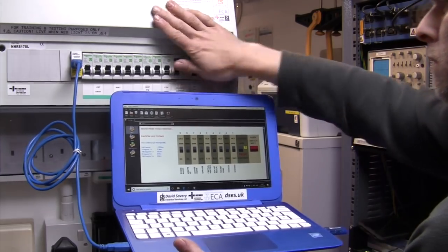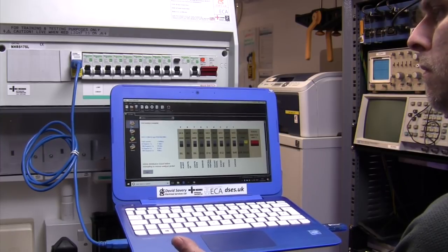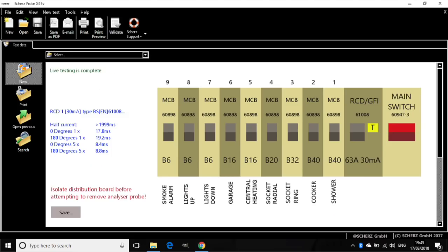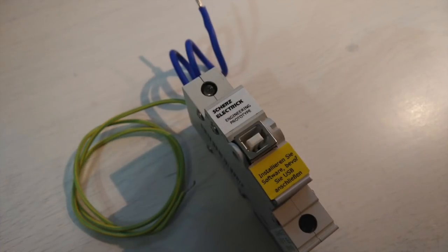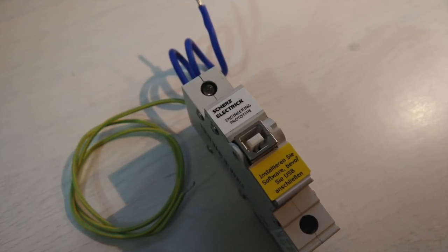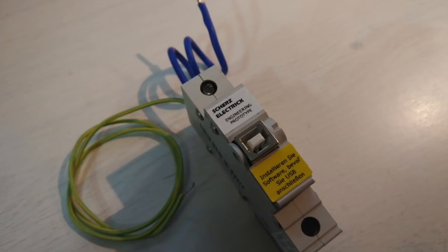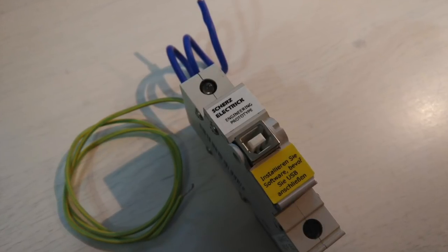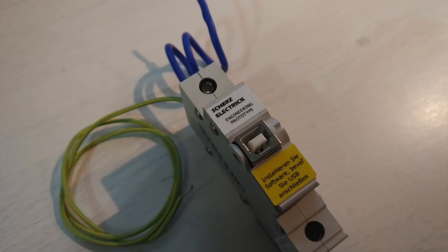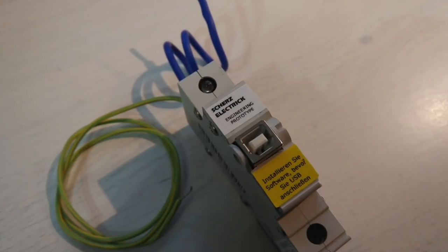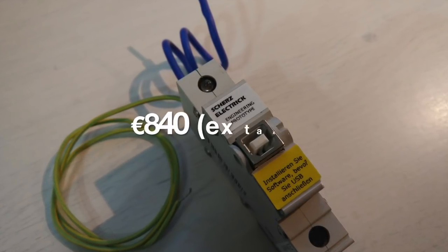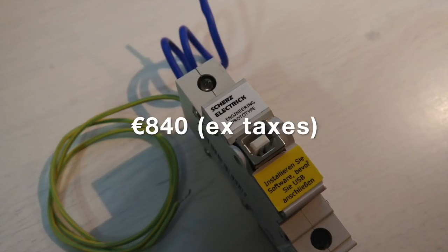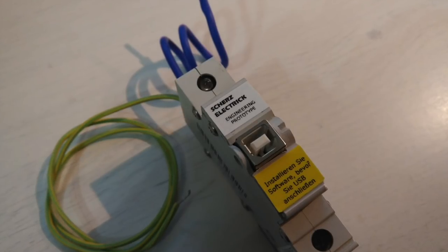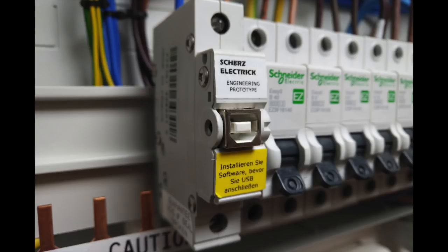Magical though it is, it doesn't do everything. Live ZS, ZE and PFC tests still have to be undertaken, as well as visual inspections, bonding verification, mechanical operation, suitability of equipment and so on. But the Scherz Electrick analyser probe gives rapid results for the most common tests with no need to dismantle the circuits at the consumer unit. At €840, the price is comparable to a replacement multifunctional tester, but the time savings on testing will be huge. Those performing regular EICRs will immediately recognise the value for money.